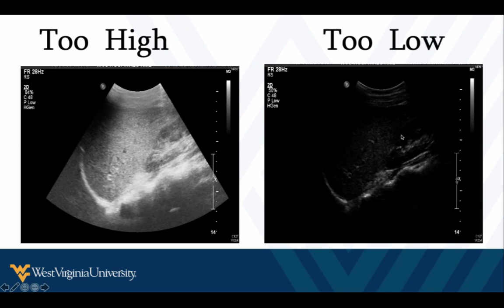Now, a lot of machines, again, depending on the machine you use, may have something called time gain compensation, or sometimes it's depth gain compensation. Those are the same thing, where you have either a physical slide rule where you can adjust the gain as you get deeper on the image, and a lot of times there is signal loss on your ultrasound, so it actually helps to have it go down a little bit of a diagonal like this, because you are losing a little bit of signal as you get deeper on your image, and some of those sound waves get absorbed into the tissues. Now, in some machines this is a virtual thing, and some machines don't even give you this option because they try to set it up automatically on their own.